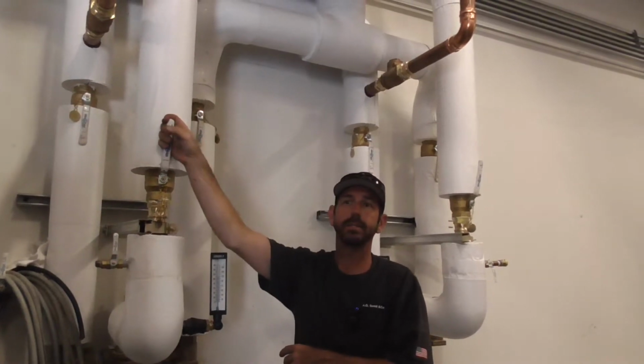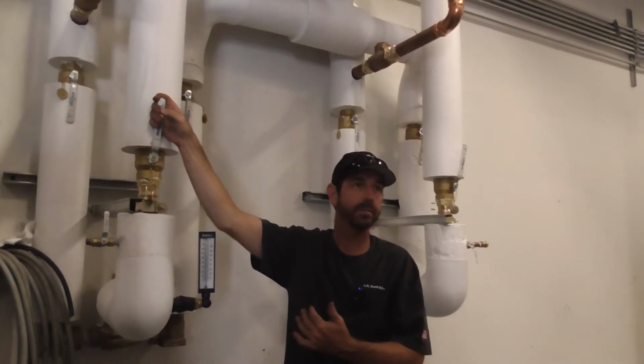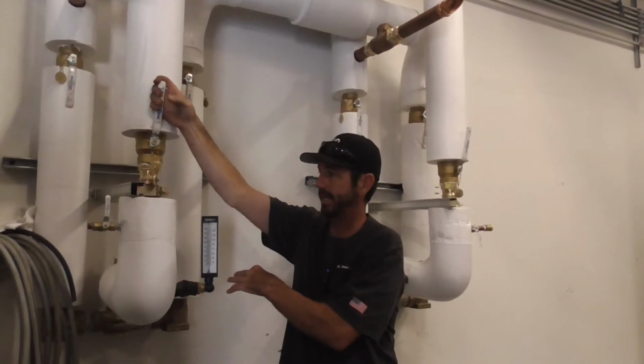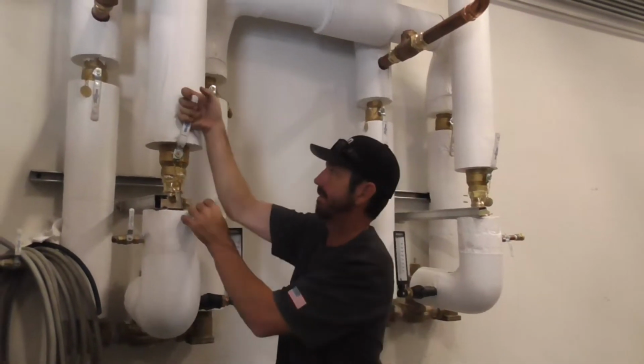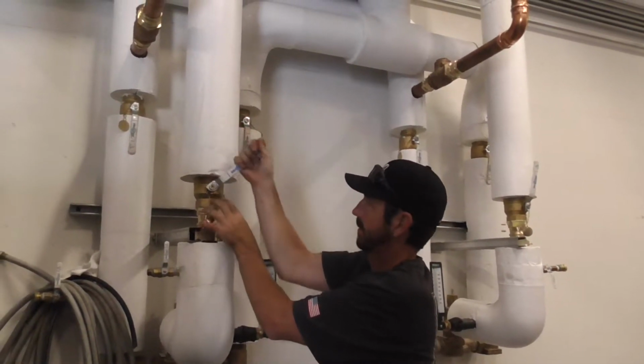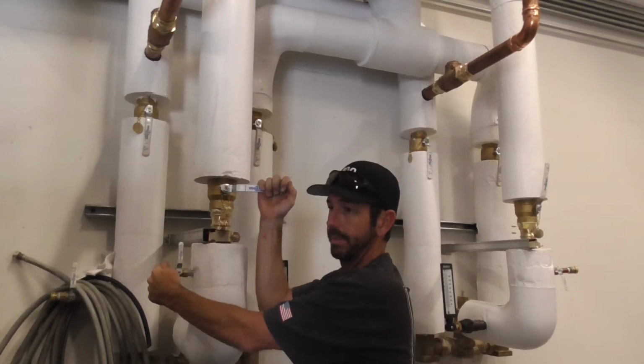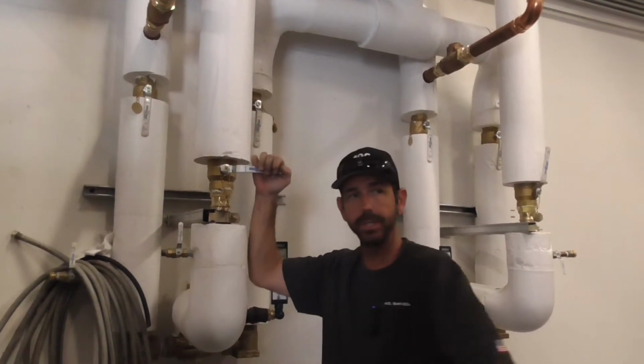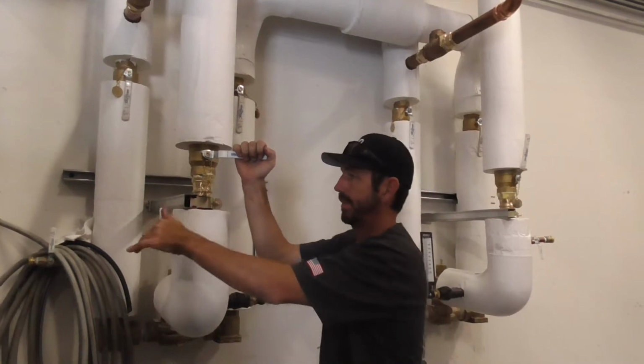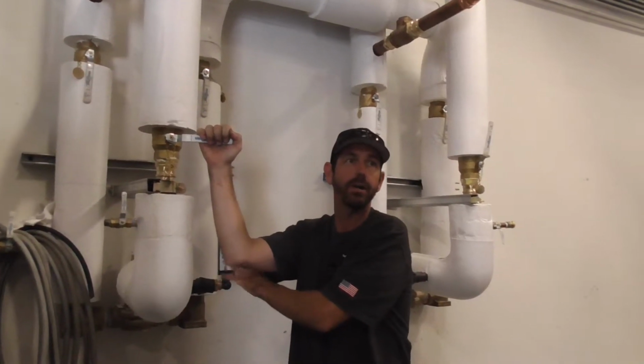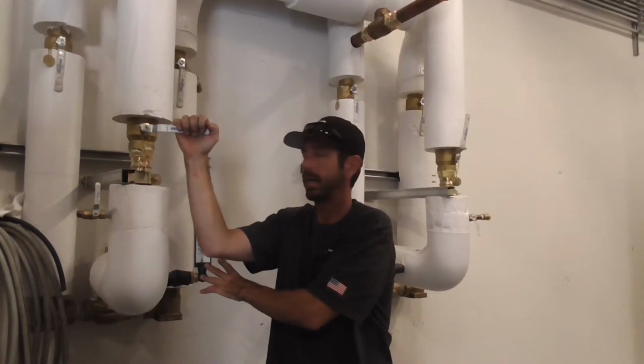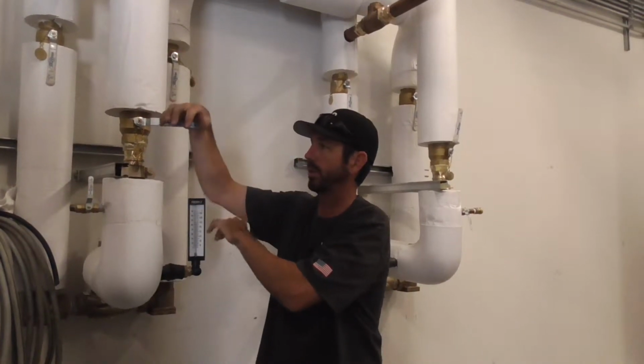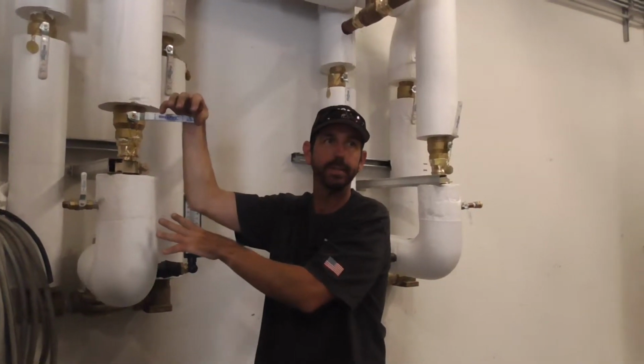I would say at least every 6 months, I would verify the setting of this. So by that, we can shut this valve right here, our leaving valve. We can stick a hose bib adapter in here and run this to a drain, and then we can open this and we can actually check our setting, okay? That way you're controlling the water that's flowing out of the device, okay?